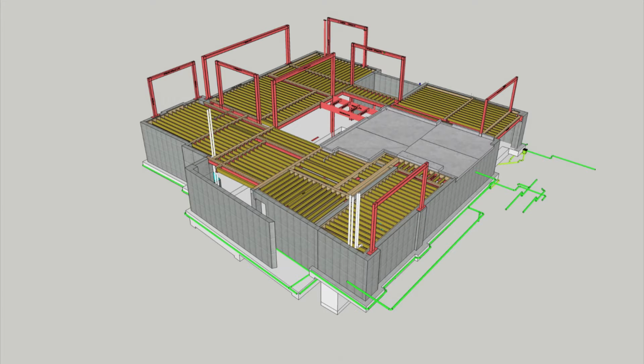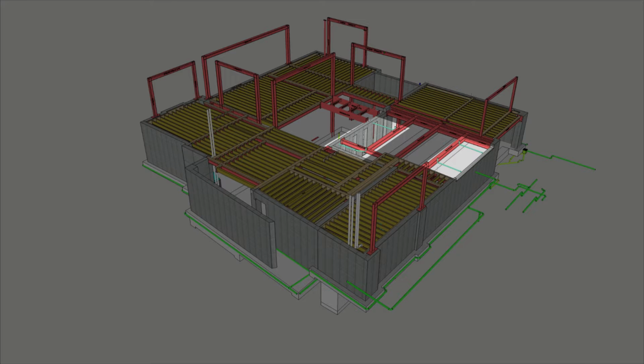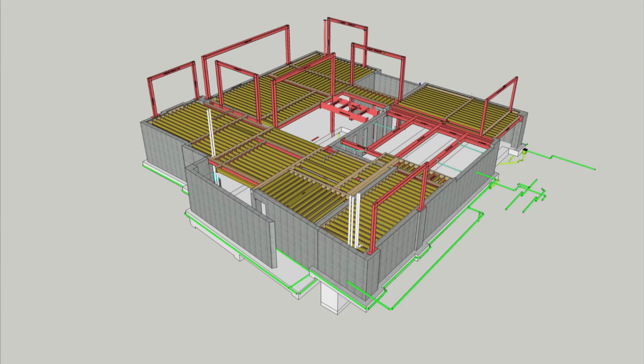There was no drainage design for this, but in researching the plans and details, it's obvious that a drainage system will be necessary. In this view, we've turned off that concrete deck layer, and you can see the drainage lines that we added in for that courtyard area. It's the light blue piping. We have found pathways for these.